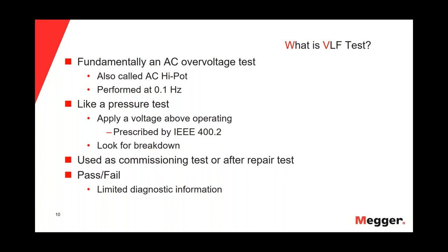In the VLF test, some standards allow decreasing the frequency. Some other standards don't allow that, okay? But normally we will say that the official frequency for the VLF test is 0.1 hertz. And the VLF test is pretty much like a pressure test. We will apply a voltage above operating. The voltage will be prescribed by a standard, for instance, the IEEE 400.2. And we will look for a breakdown.